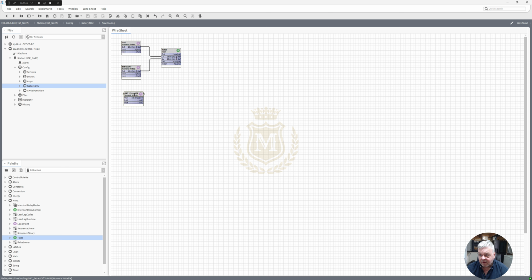So OAT underscore extract, done that in capitals there, extract differential, and actions set, we want 2 degrees differential. Let's set that to 2 degrees on here. So up at the top there, let's go down to our temperature, put it to C for degrees. We'll take out the position. No, we'll leave the position in, and let's say we can do a minimum of 0 and we can't go any more than 10. No, that's going to be a lot. Can't go any more than 4.